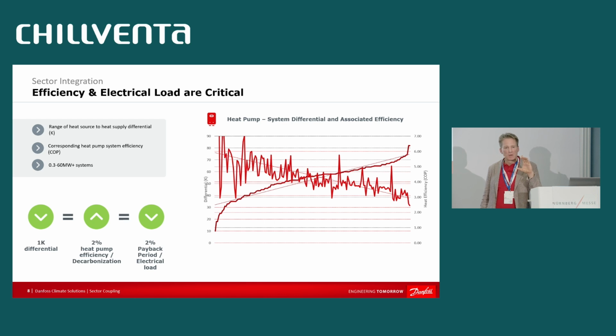That ratio is ultimately critical to an electrified energy system, because if you don't exceed that ratio, what do you not have? You don't have a payback. So if your spark spread ratio is 2.5, and your heat pump system's efficiency is not 2.5 or greater, you have no payback. The magnitude of that difference governs the payback period, and ultimately the decarbonization potential, because you use less electrical energy as a result, if you exceed that ratio.